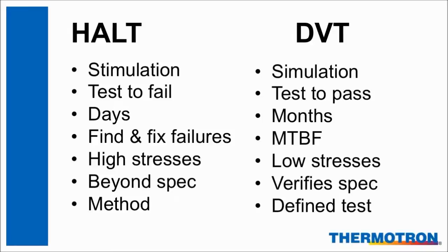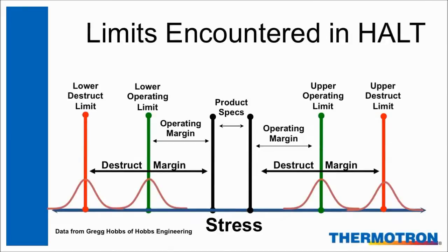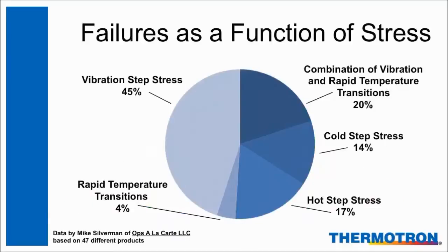This graph shows a narrow range in the center, which signifies the product's normal use specifications. This is the range where the manufacturer warrants that the product will work. Outside of the product specifications are the upper and lower operating limits, when the product will stop working. If the stress is backed away from these limits, the product will begin to work again — it was not broken, just inoperable. The final limits are the red brackets that signify the destruct limits. These are the points which, when passed, the product breaks and will not work again until it is fixed. This pie chart is a summary of product failures from 47 different HALT tests done on a variety of different products. It shows that a vast majority of failures are found during vibration step stressing and the combination of temperature and vibration phases.